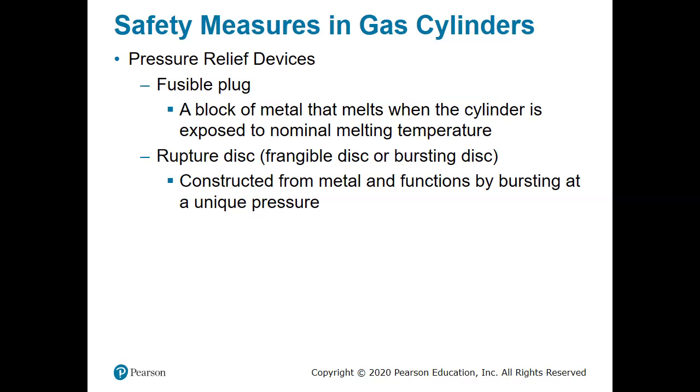First is called a fusible plug. The fusible plug will melt at a particular temperature, and it will open up a pathway for the gas inside of the cylinder to get outside of the cylinder. Now, that particular temperature is considerably higher than room temperature. Again, it really only gets activated in the event of a significant fire.